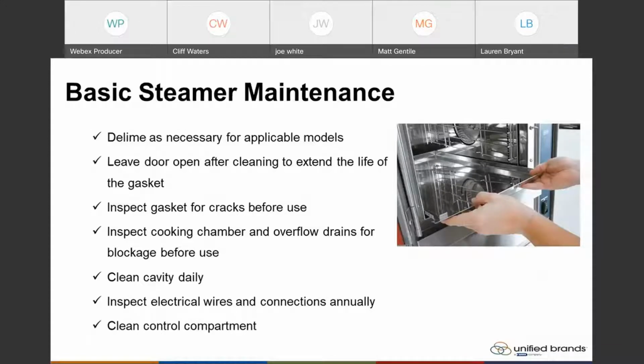Basic steamer maintenance: deliming is necessary for applicable models. Leave your door open after cleaning to extend the life of the gasket. Inspect the gasket for cracks before use. Inspect the cooking chamber and overflow drains for blockage before use. Clean your cavity daily, and inspect electrical wires and connections annually.